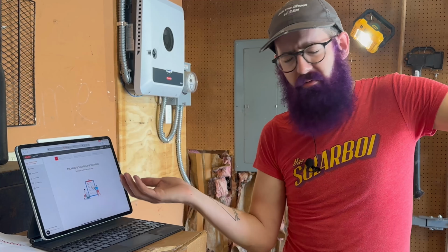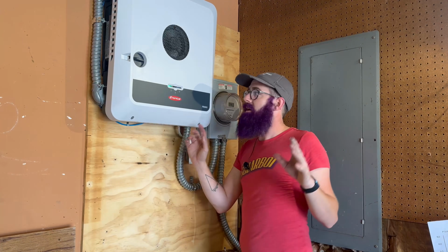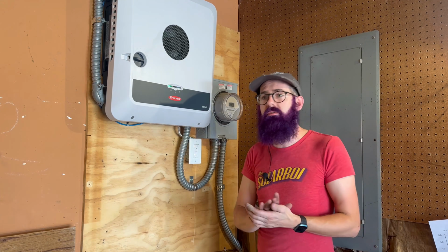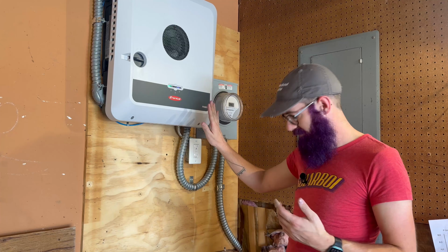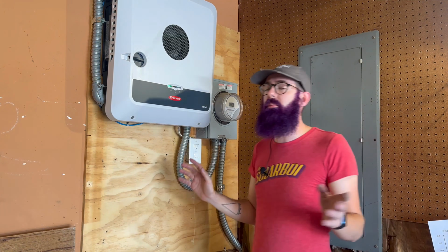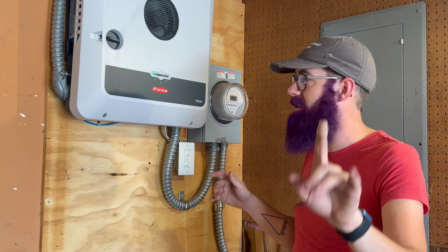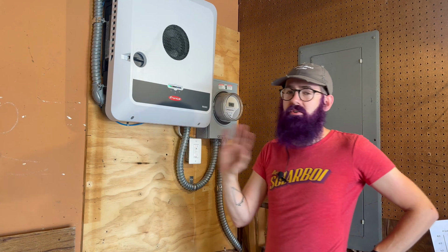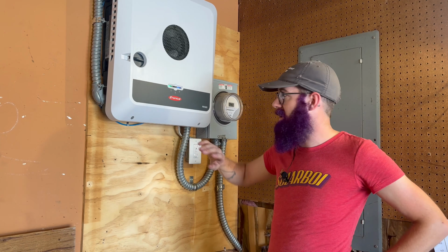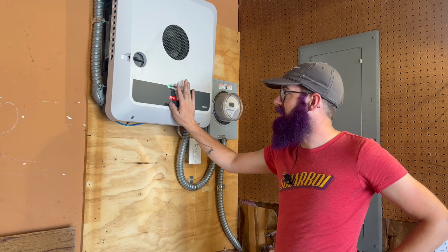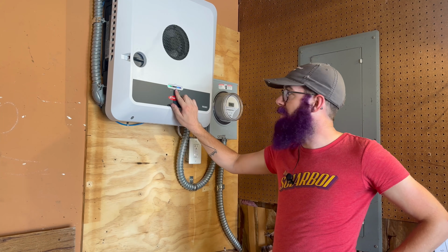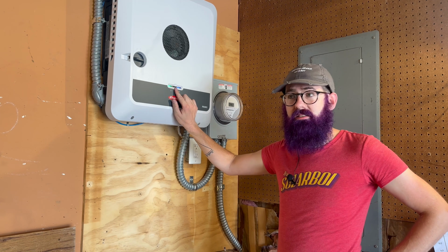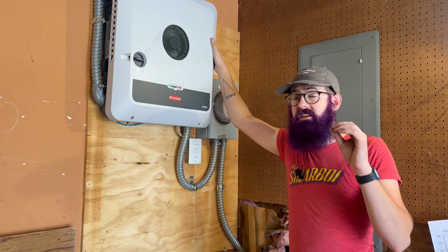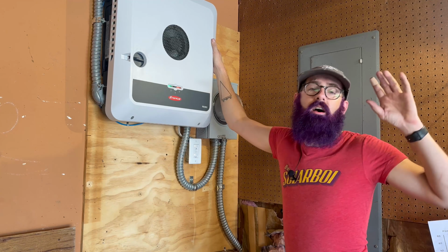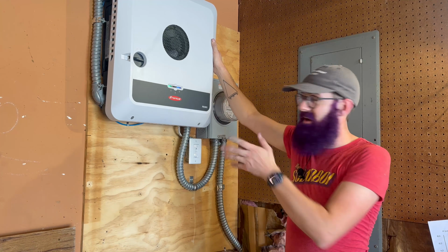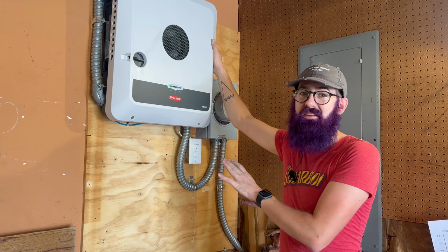It's a good resource, flat out. And by the way, if you have a fault code you need to manually clear on the inverter, say an erroneous arc fault pops up, which you probably won't, you don't want to keep going back to site just to clear it for the customer. You can have the customer come over, hold this button for 3 to 6 seconds, and it'll clear. Even if you just need it cleared for a day before you get there, that's a really nice thing to be able to do.